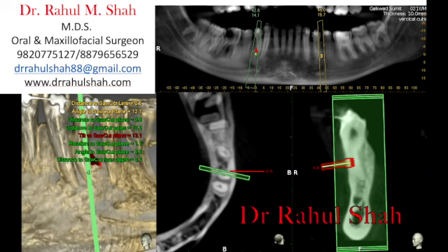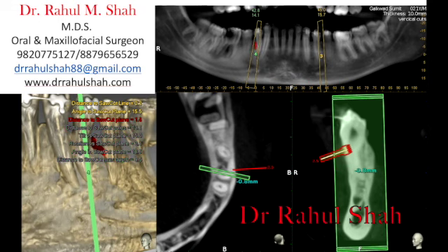This machine being a very portable machine, I carry it to different operation theaters in different hospitals where I consult. Because of the trace protocol, there is no need of taking a navigation with any fiducials in the mouth. Any CBCT or a CT scan can be used for planning and executing of these surgeries.